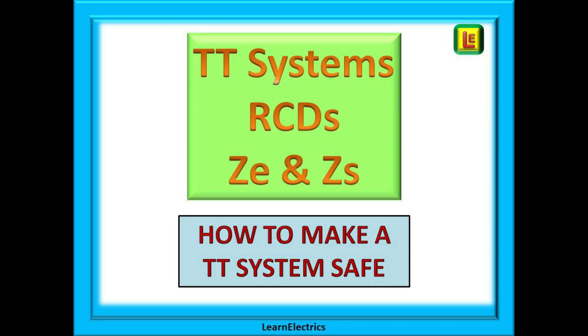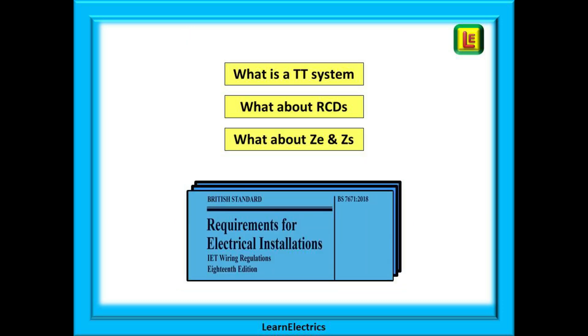Welcome to LearnElectrics and our video on TT systems. We all know that TT systems need special consideration, not least the fact that during an earth fault the fuse is unlikely to blow, or at best it might operate very slowly outside the required response times. First we will briefly remind ourselves what a TT system is, then we will look at the importance of RCDs in TT systems, also at the weaknesses of this type of system, and finally we will cover the subject of ZE and ZS in TT systems.